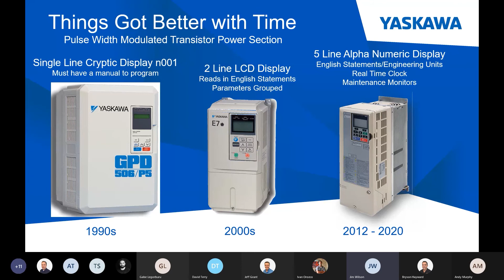In 2012, the Z1000 came into the market with a much better display, a 5-line alphanumeric display, English statements, and engineering units. We added a real-time clock so you could time and date stamp faults or alarms, and you could even change the set points based on the time of day for smaller applications where you don't have a building automation system. We also added maintenance monitors to eliminate spare parts issues, so now you can go look at the drive and see what parts are aging, and decide whether to get one on hand or be ready for that event.